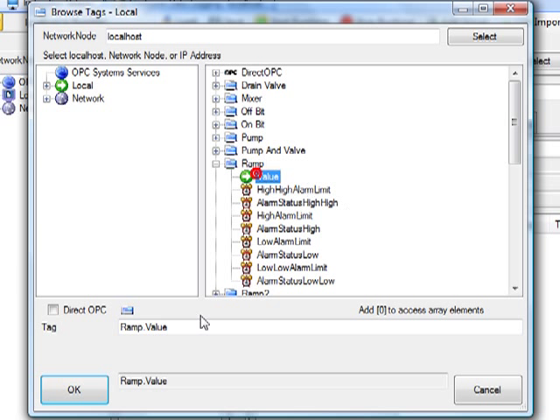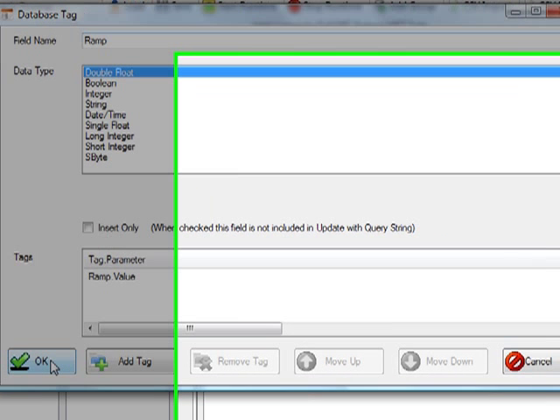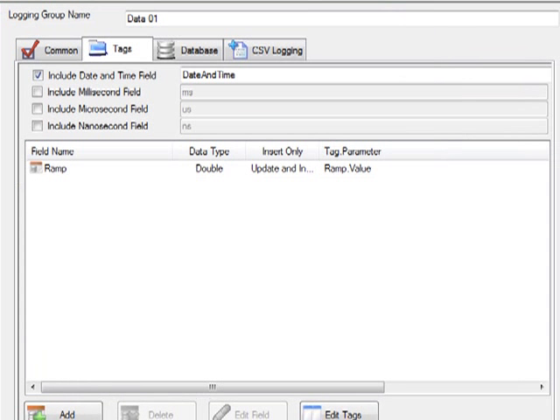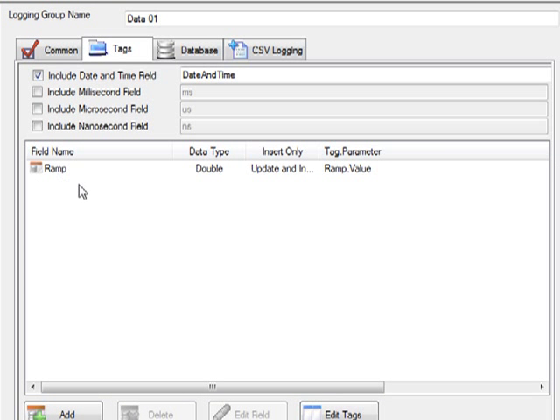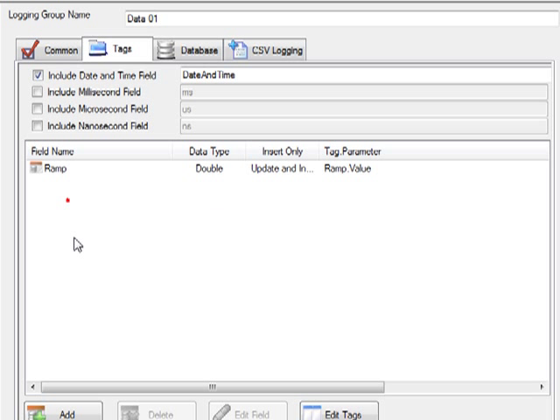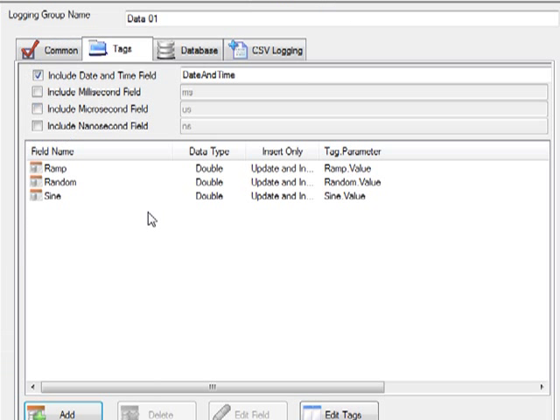Here I'll select ramp value. I'll click OK. And here is where I can specify the field name. I'm just going to use the field name called ramp. I'll specify the data type, I'll use the default of double float, and click OK. So that's one of the points that we're going to log. If you needed to set up a lot of points, you can use a CSV import and export feature. I'll select a few more points from the configuration. And there we have three points we can log values for at a one second interval.